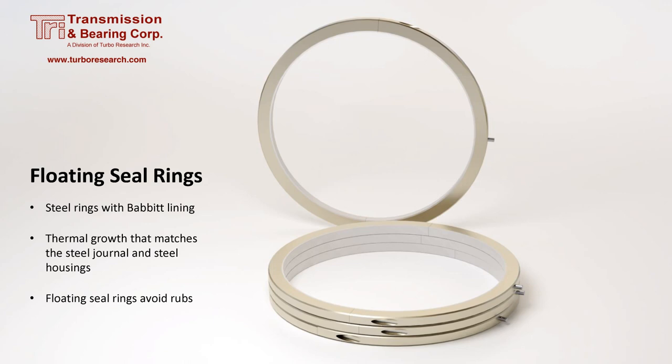An upgrade design uses steel-backed seal rings with babbitt bores. These seals have two halves that bolt together, so the garter spring is not required to keep the ring in the proper circular shape. The garter springs are only required for axial forces when the seal oil pressure is low — for instance, at startup. With seal rings that are bolted together, the springs can be less stiff because they are not required to keep butt joints together. More flexible springs means the axial forces pushing the seal ring against the housing are reduced, allowing the seal rings to move more freely in response to rotor vibrations.